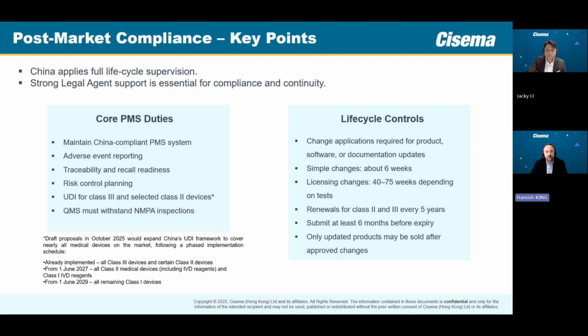Renewals as well. There's a 5-year expiry for Class 2 and 3 products. You need to submit your renewal at least 6 months before expiry in order to maintain the certificate currency. The other thing to say about post-market is NMPA is doing more and more inspections and audits, surprise audits, where NMPA will take a product being sold on the market, send it to a test lab, and check the results of the testing versus the product technical requirements.